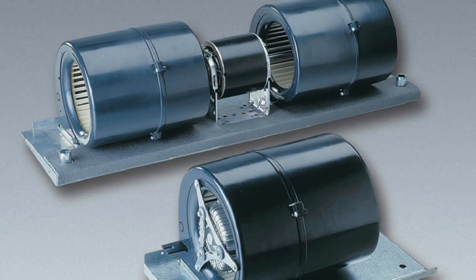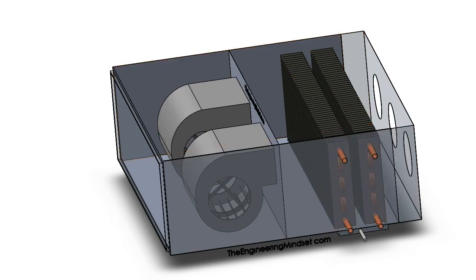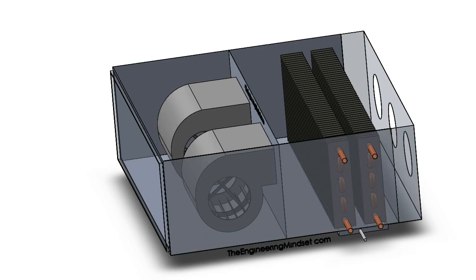In the real world, fans look like this — two fan chambers mounted to one motor, or a single fan with its own motor. The heating and cooling coils do not necessarily have to be on the discharge side of the fan; it varies by manufacturer. The coils could also be positioned before the fans, so the air passes through the filter, over the coils first, and then is sucked by the fans and pushed out.